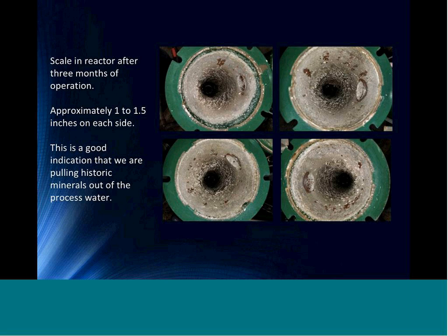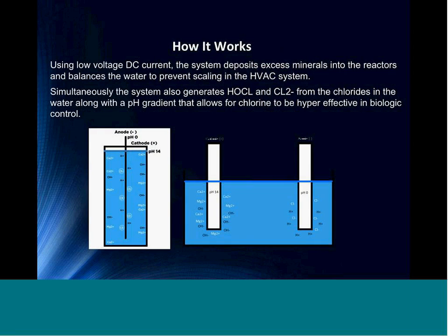We don't require those. This material was formed in about 3 months, and we usually go in the first 1 to 2 cleanings manually removing it so we can do a mass balance and double check how much mineralization we're pulling from the water versus what we calculated in our water testing. And we keep that in balance. Once we've established the baseline parameters, our system is pretty much plug and play and runs very well. We do an inspection once a month, double checking everything, and then the site will do water chemistry several times a week just to see that the water chemistry is staying in compliance. The nice thing is we are also generating chlorine and hypochlorous acid, which is measurable, so that according to CTI standards, we can achieve basically the regulations that most people are observing. Next slide, please.